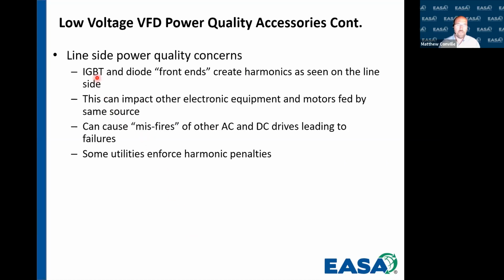With our IGBTs and diodes, these front ends are going to create harmonics, just like I showed you. This can cause an impact, especially on very sensitive electronic equipment and other motors that are fed by the same source. If we have multiple drives fed by the same feeder, like a main breaker that goes into an MCC, and we have 10 or 15 drives, we can cause misfires of those drives because of all that notching that we've put on the line by not taking care of that harmonic content. Some utility companies actually enforce harmonic penalties. As drives become more and more commonplace, I really expect to see, and this is just my opinion, that the utility companies are going to have a more strict approach to harmonic content, mostly because they're not going to want to put in the infrastructure themselves to account for that from their users.